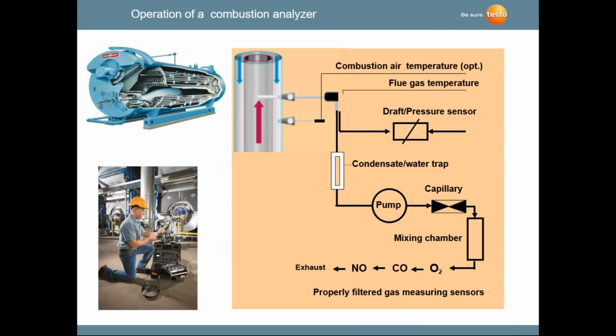You're all familiar with the design of combustion analyzers. I just want to bring to your attention that there's a probe and hose attached to the analyzer. The probe is in the stack, and the thermocouple wire sticks out at the tip of that probe. So we're getting instantaneous temperature measurement, and we have a pump in the instrument that is actually drawing the sample from the stack in through the probe and hose assembly, through a water trap, and the last place that the flue gas goes is actually into the sensors: the oxygen sensor, the carbon monoxide sensor, and the NOx sensor.